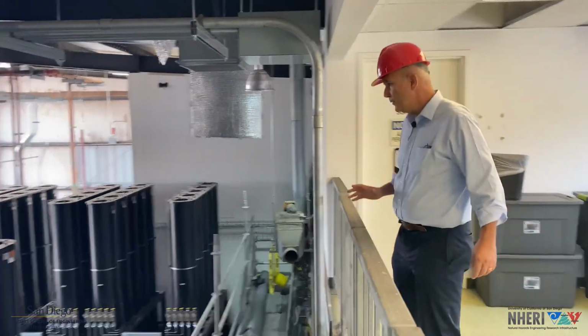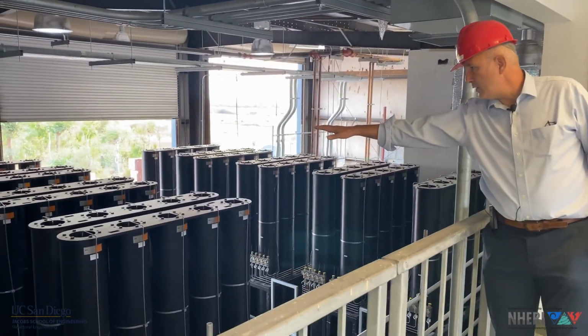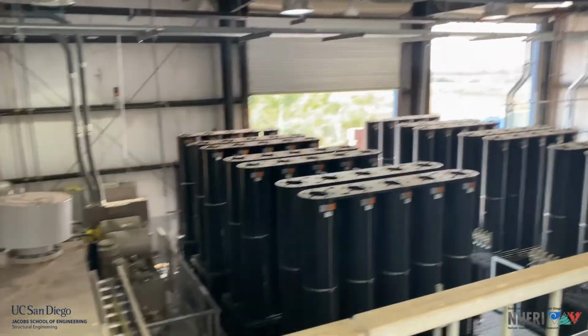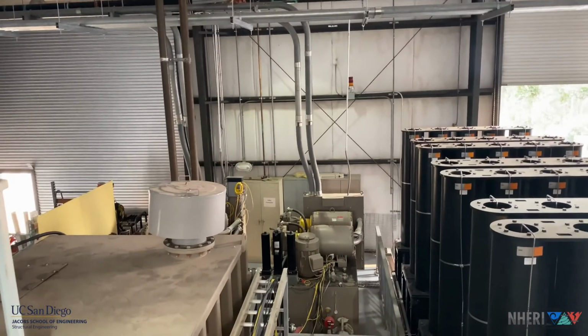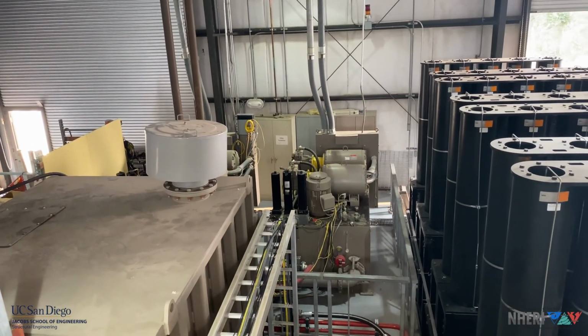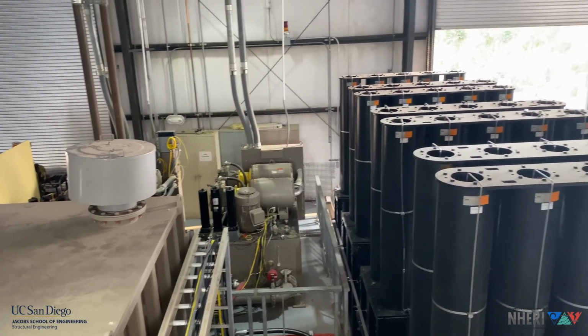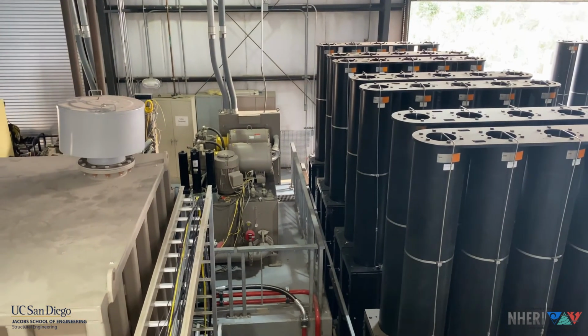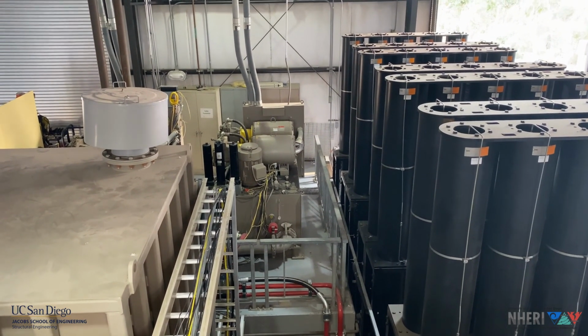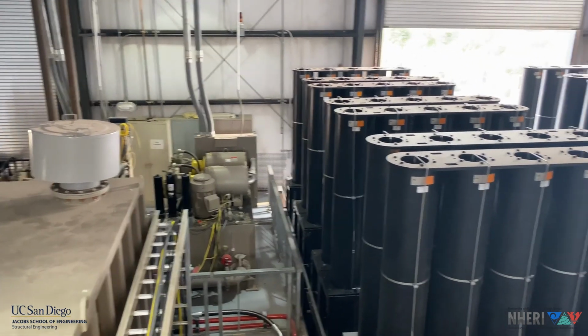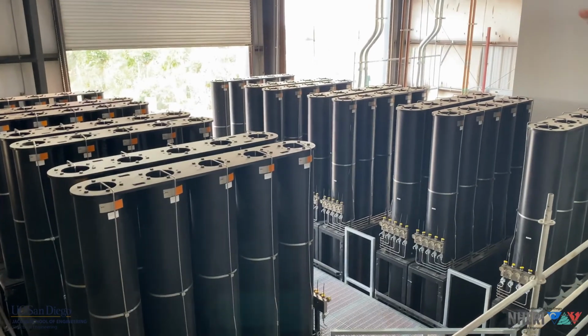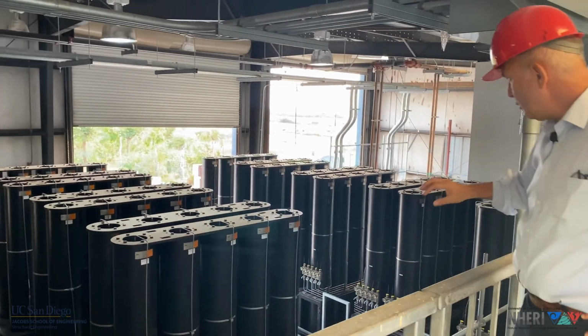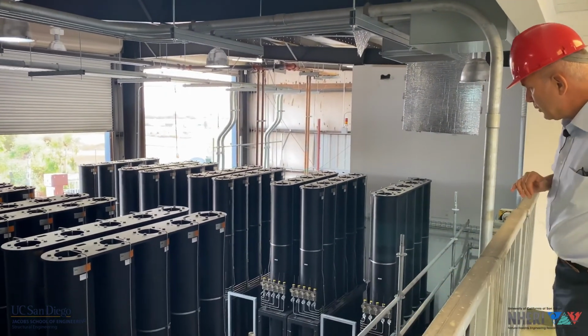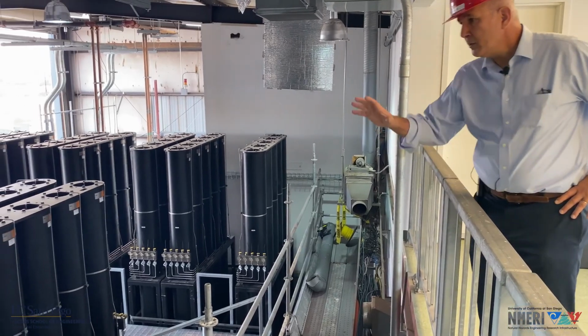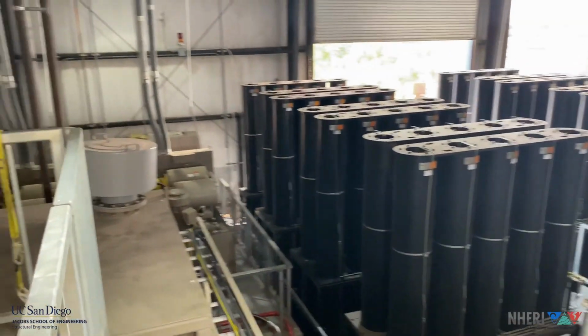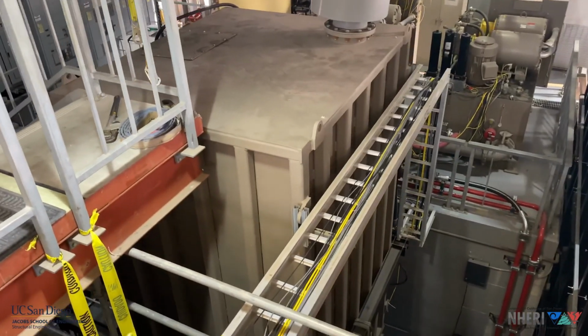So here we have a very good view of, first, the 2 existing pumps. One of them is going to continue to serve as the pump that is feeding all the pilot flows to control the spool of the servo valves. And the second pump will also be used to pressurize the accumulator bank. So we will have 3 pumps to pressurize the accumulator bank now. You see the top of the accumulator bank, again, these modules of 5 bottles each, 15 modules, 75 bottles. You can see again the surge tank here. It's a 20,000 liter surge tank.